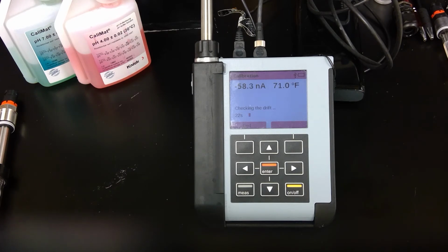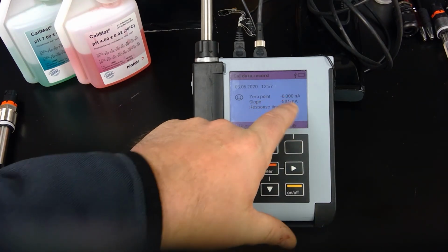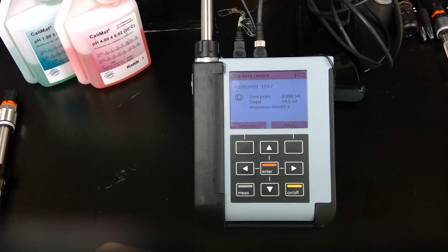So again, making sure that you're already polarized, so that way once it goes into the field, you're not going to have to worry about any kind of drift out of the electrode. So we should be coming up on the calibration results here. And so far it looks very good. And this would also apply to this SE715, this type of calibration, as well as the SE707. So all three of those are Clark cell, amperometric Clark cell sensors. This would not apply to the SE340 or the SE740, which are luminescent dissolved oxygen. So you see my 0 point is 0 nanoamps, slope is minus 59.5, response time 60 seconds. I go ahead and hit apply.